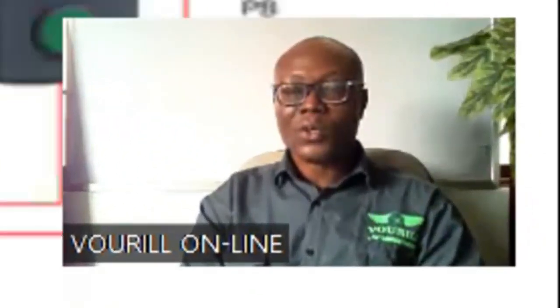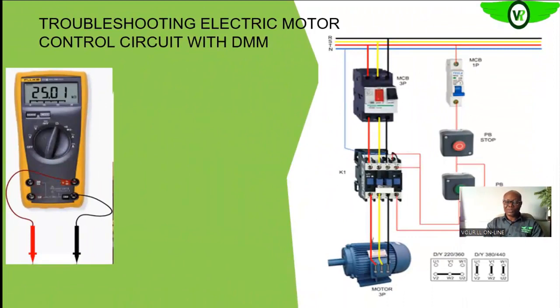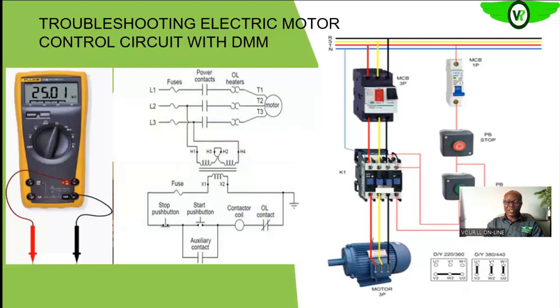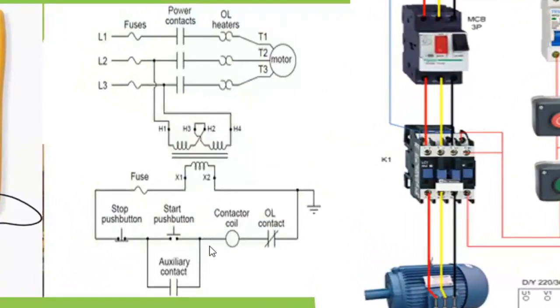Still on the electric motor circuit, we have discussed earlier how to troubleshoot the electric motor circuit. Let us explain a little on this one that is a little bit more complex than the one we observed earlier, in the sense that we have more components in the system. If you look at this, on the power line, from the input into the system, we have the fuses. That's the first component we come across. Then we have the contactor, and the overloads, that help us to protect the motor against sustained overload.